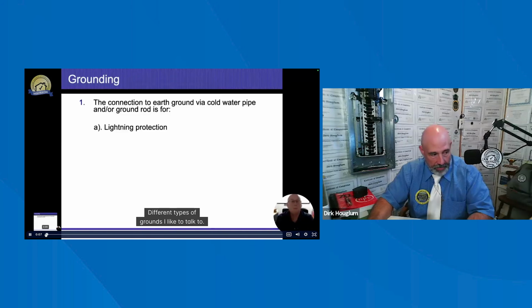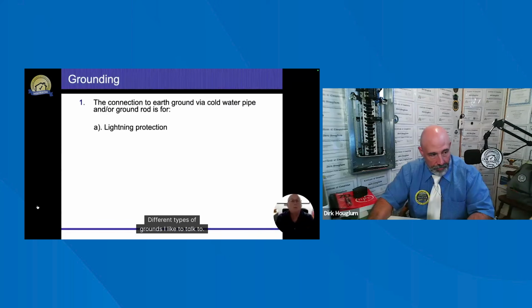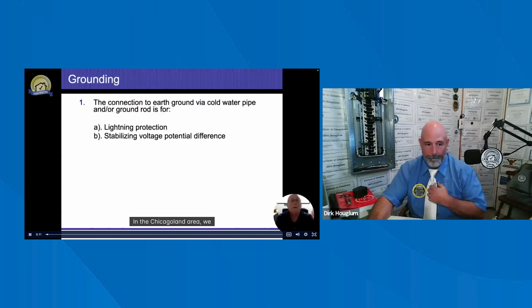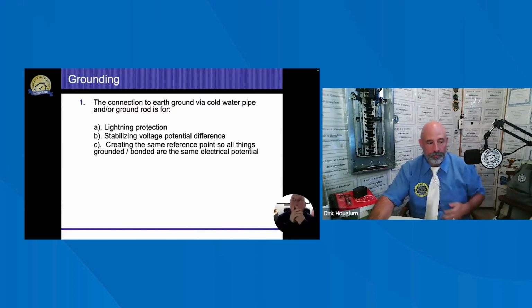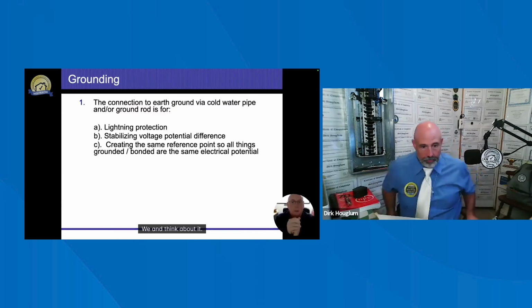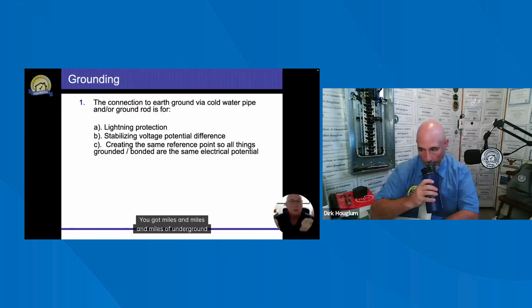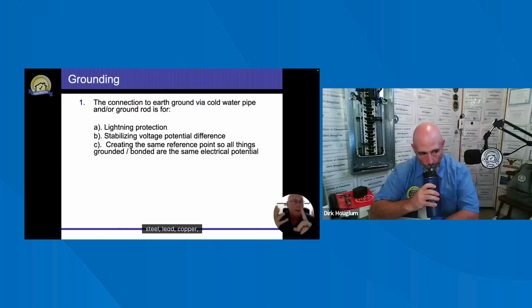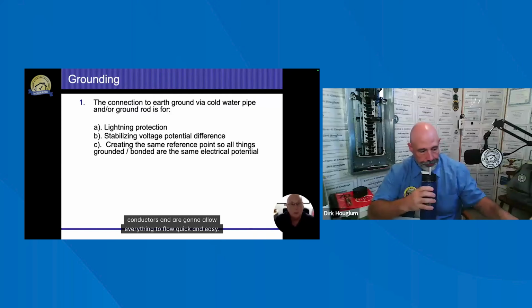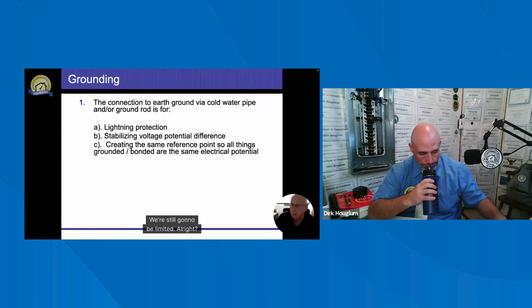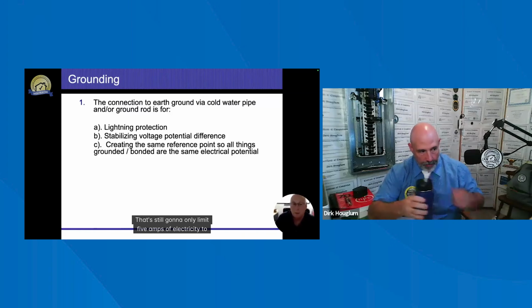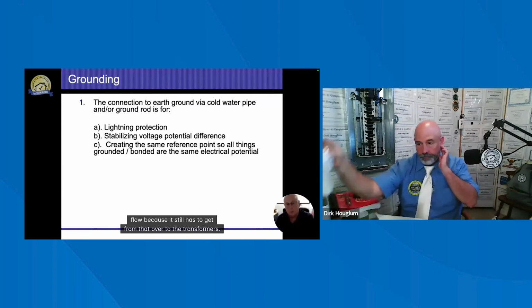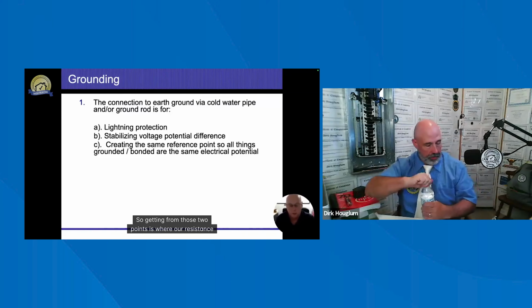Different types of grounds, I'd like to talk about. In the Chicagoland area, we use water pipes. And think about it, you've got miles and miles of underground steel, lead, copper, unlimited pieces of metal that's underground, which are fantastic conductors and are going to allow everything to flow quick and easy. We're still going to be limited. That's still going to only allow 5 amps of electricity to flow because it still has to get from that over to the transformers. So getting from those 2 points is where our resistance is going to end up being.